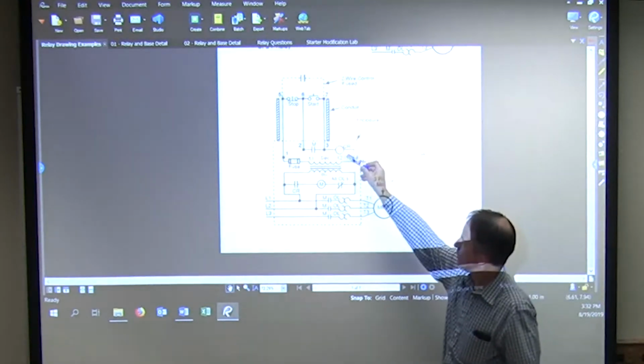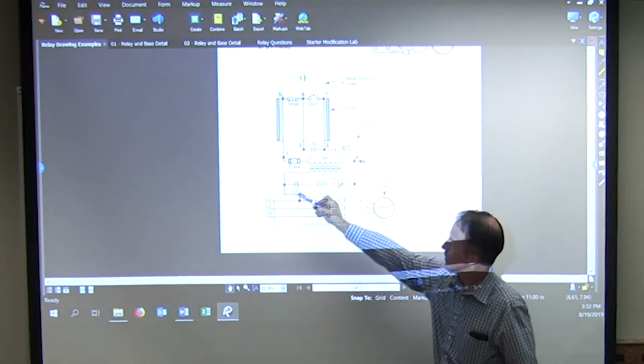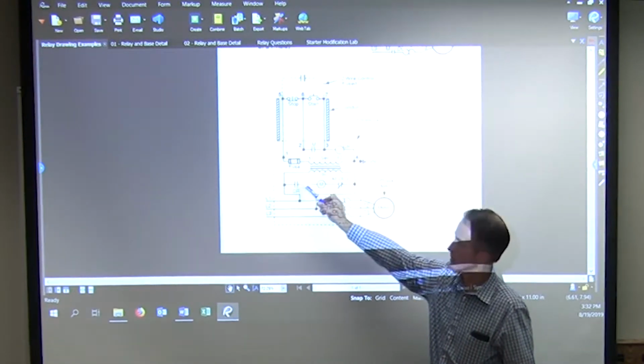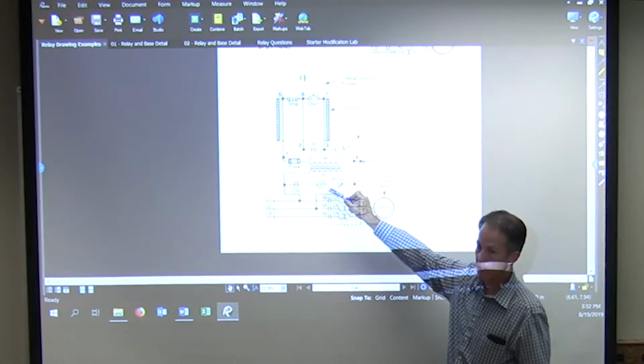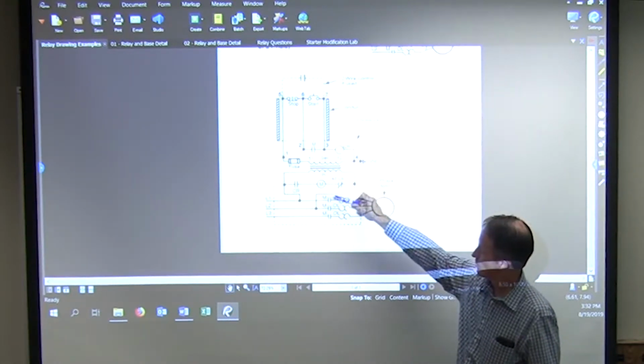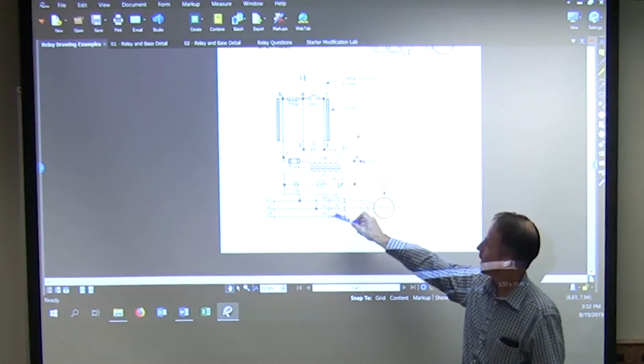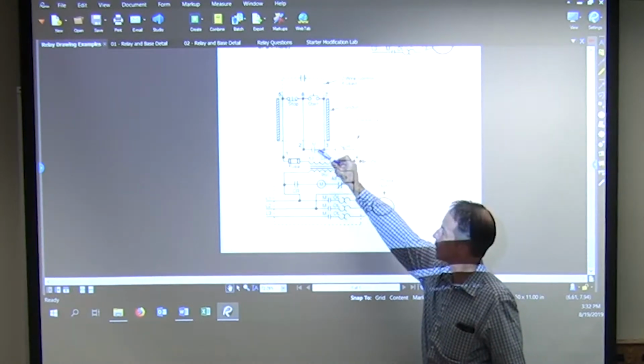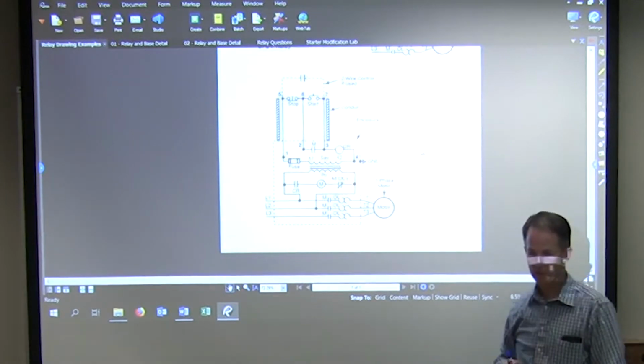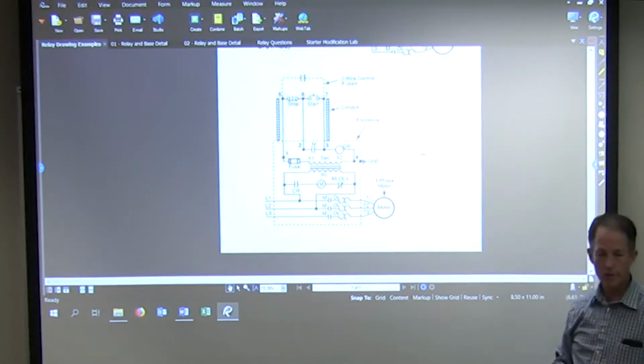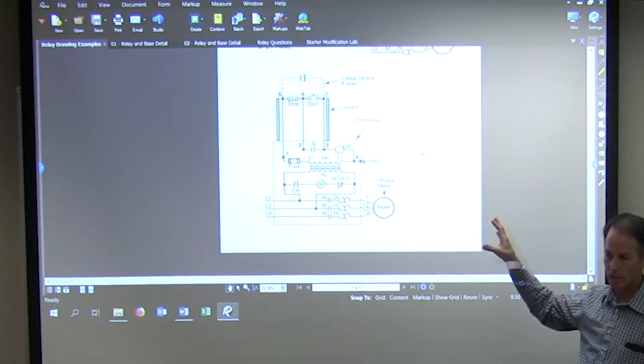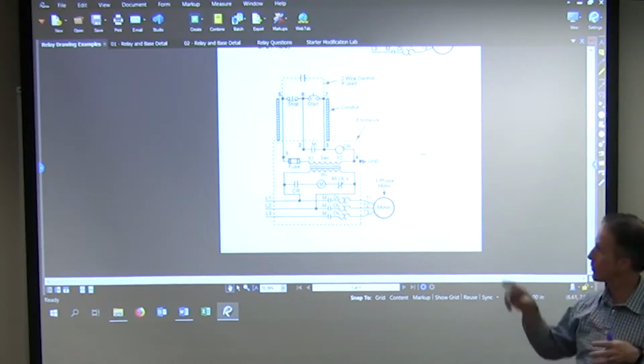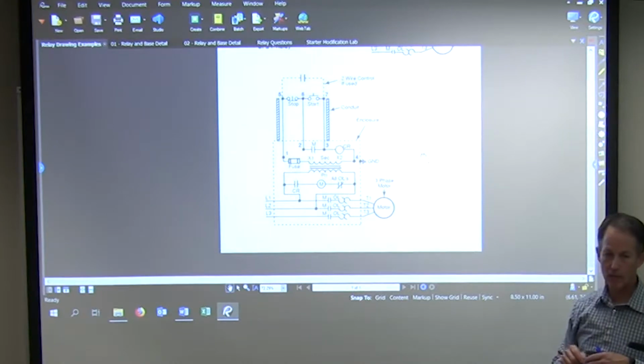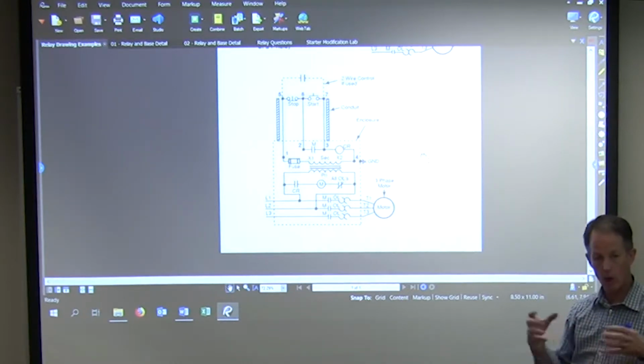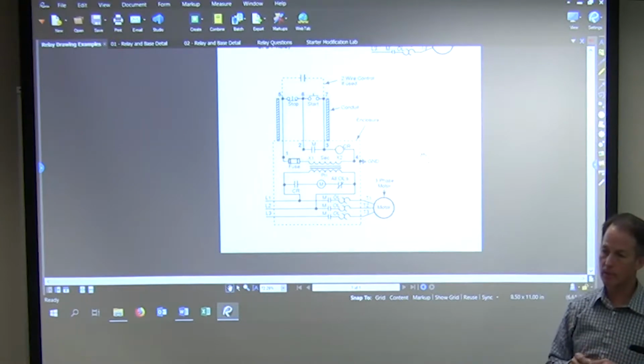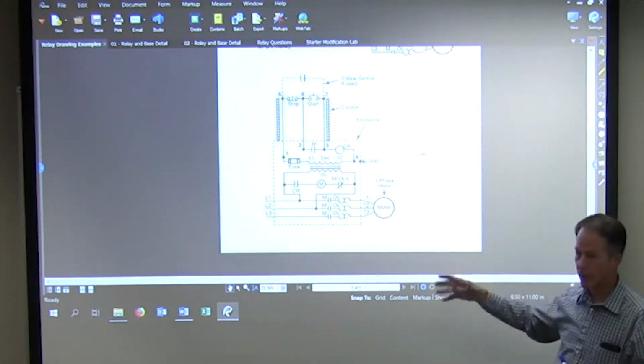Okay, CR pulls in, which closes the CR contacts, which energizes the main contact, pulling it in, and the motor starts. M also sets up its holding circuit between those two and three. What do we call that contact? It's a holding contact. So this is essentially a latching circuit. In other words, once I engage it by pressing the start, it has a mechanism to keep itself running or on. I don't have to keep holding the button. Okay. Now, we're running.